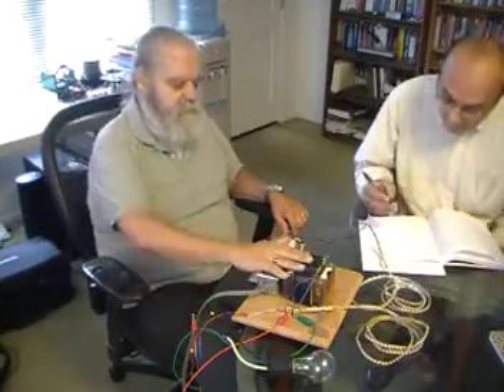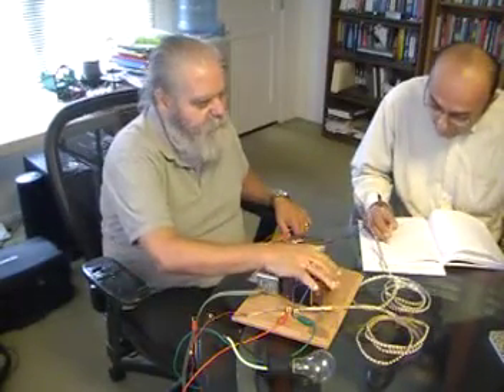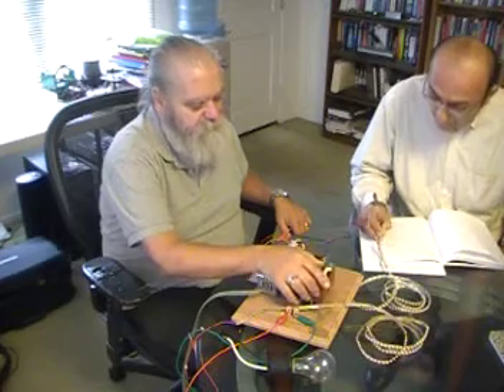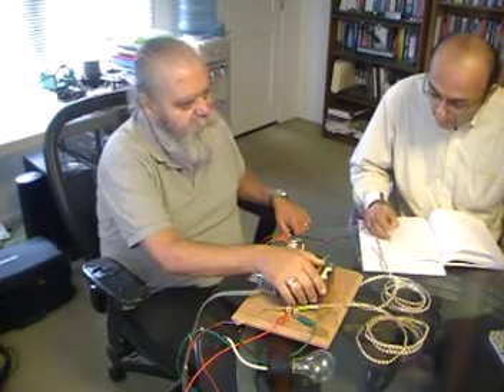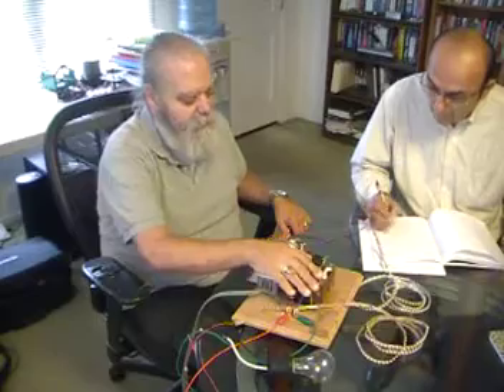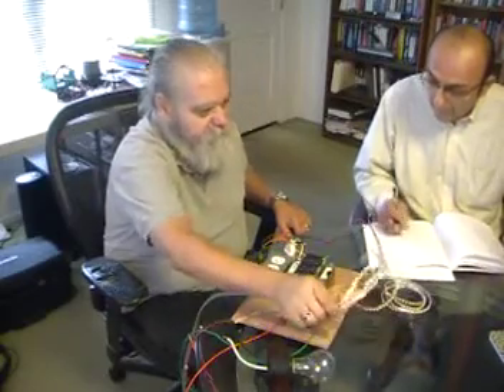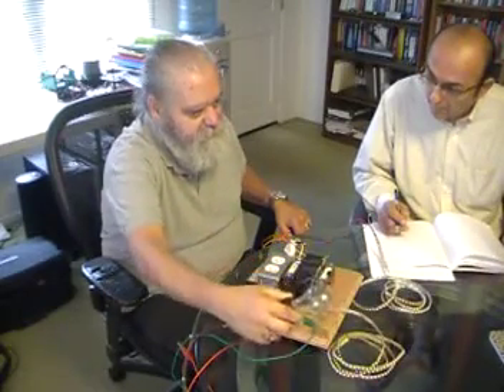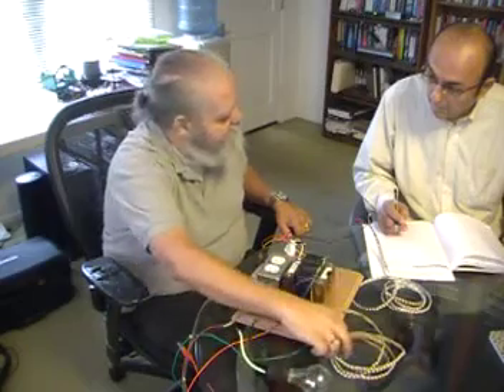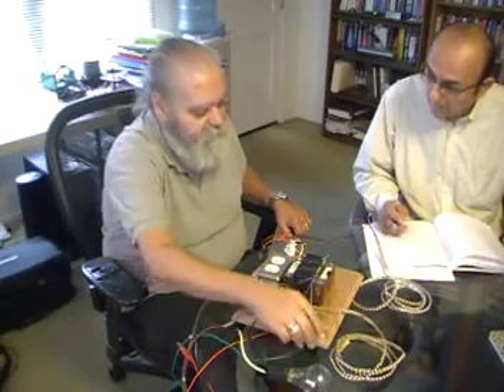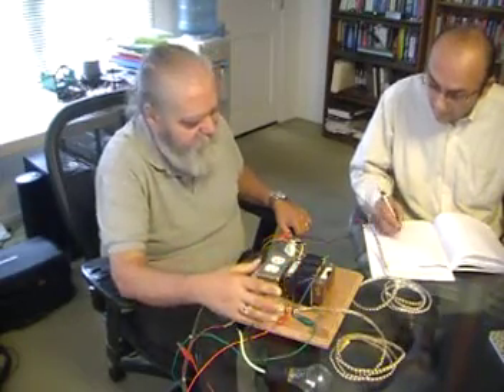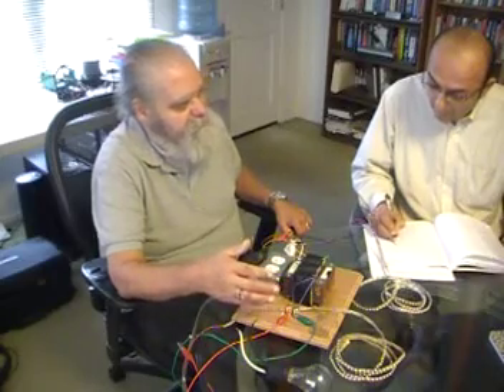The advantage of this is that because it's not a fixed ratio device, you don't get the heat generated in a standard transformer, because it only supplies as much power as the load can take. So this is the upper limit, this is the lower limit, and the end result of being an adaptive device is you don't generate any unnecessary heat.